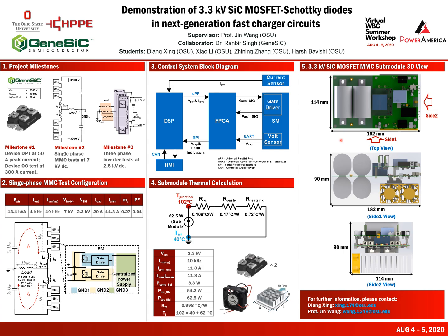The 3D drawing of the MMC sub-module is shown on this page. From the top view, you can see we have 4 sub-module capacitors here. The upper PCB is the voltage sensor, and the lower PCB is the gate driver. We use fiber optics to receive the gate signal and send out the fault signal. For the thermal design, we have 2 fans and 1 heatsink for each sub-module.